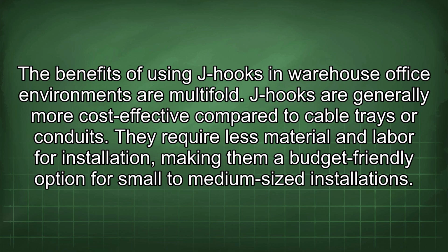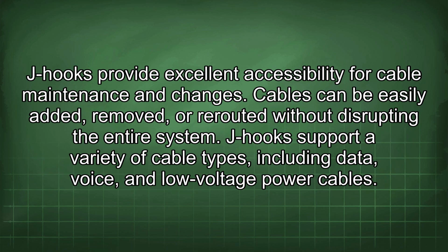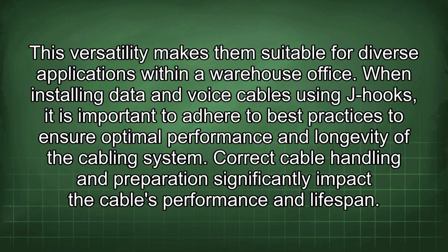The benefits of using J-hooks in warehouse office environments are multifold. J-hooks are generally more cost-effective compared to cable trays or conduits. They require less material and labor for installation, making them a budget-friendly option for small to medium-sized installations. J-hooks provide excellent accessibility for cable maintenance and changes. Cables can be easily added, removed, or rerouted without disrupting the entire system. J-hooks support a variety of cable types, including data, voice, and low-voltage power cables. This versatility makes them suitable for diverse applications within a warehouse office.